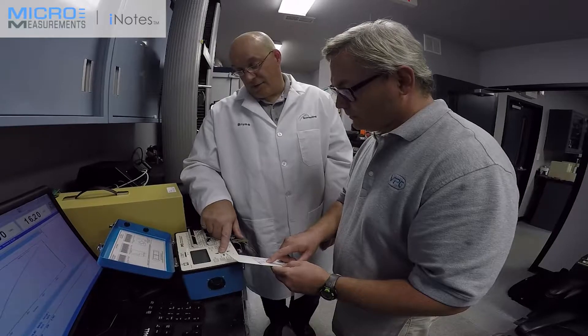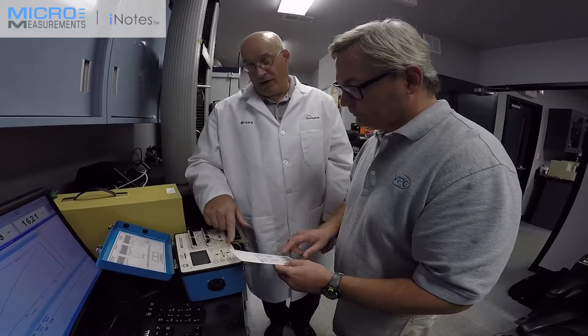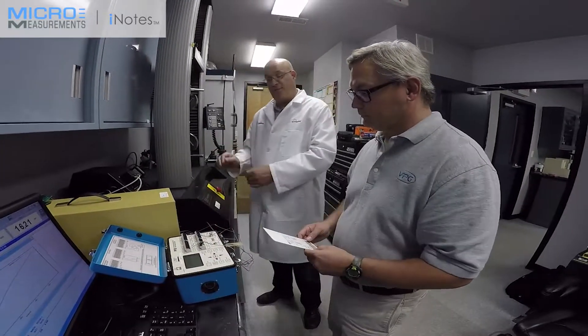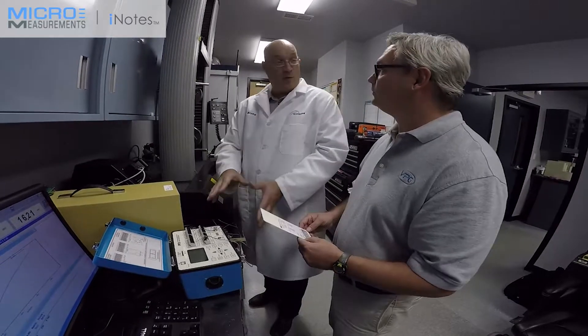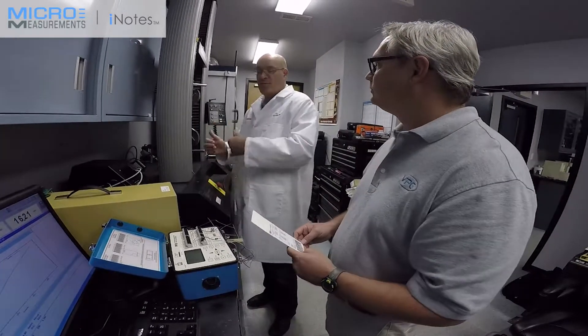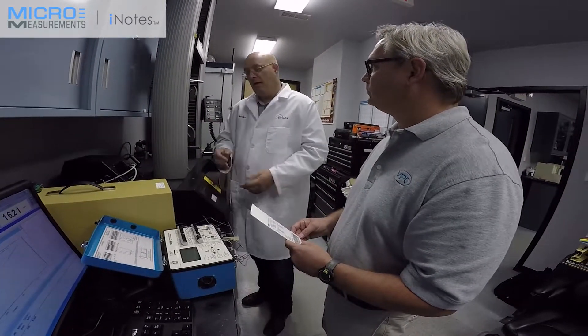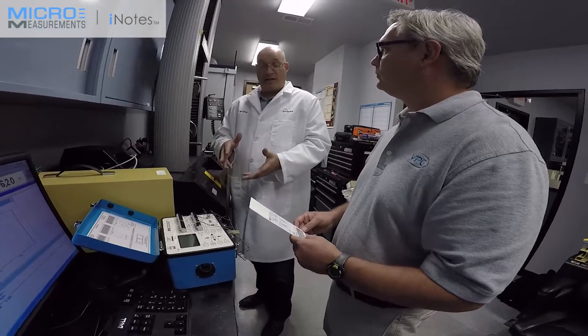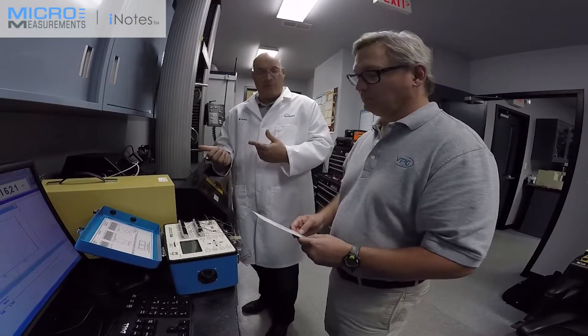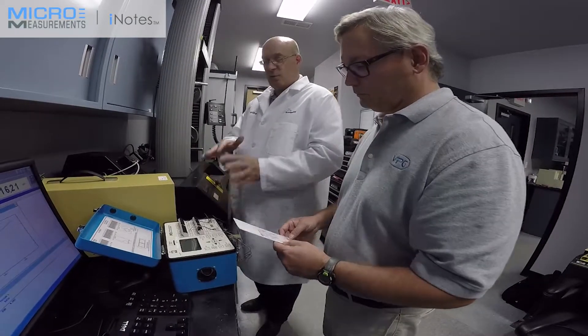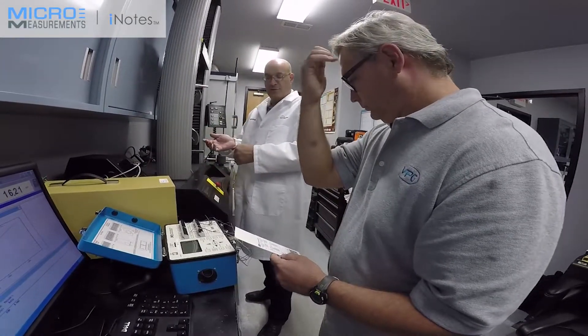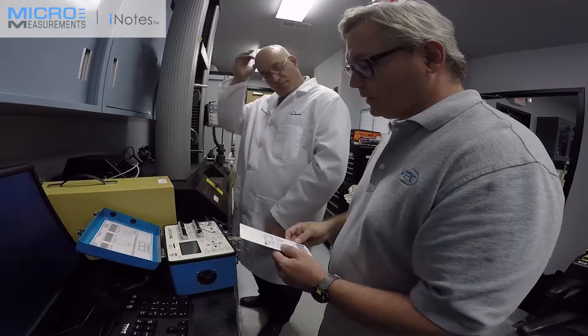Now that the value is in, we're basically, the only thing we have to do is load the specimen, zero our strain before we start, because as we load the specimen, we're going to induce some strain, which could be, in this case, we might want to measure that to see if we load the specimen properly. But in most cases, we want to zero it, assuming we have loaded the specimen properly and start the test.